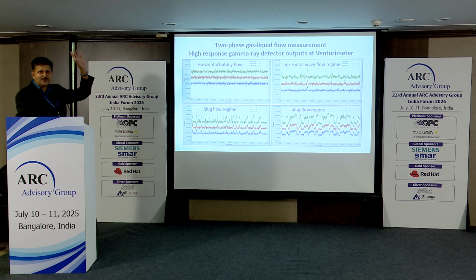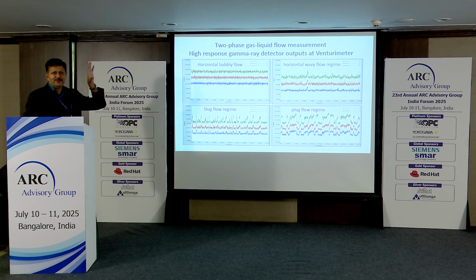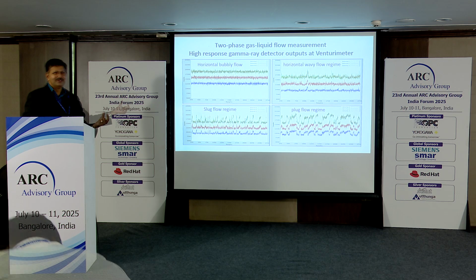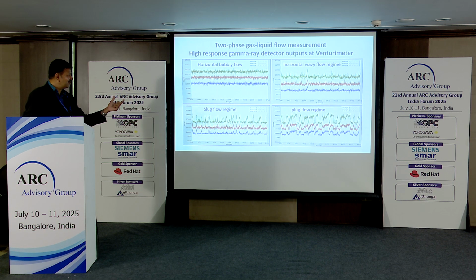It is a very classic design, like the old 1960s Framo design. So you have the mixture coming in to the homogenizer, and downstream of that, the gamma ray attenuation detection system is at the throat, so that you know exactly what is happening with the densitometer. Now the output is from the densitometer, and you can see that by observing the signals from the densitometer with high response, the x-axis is the time axis with data captured at 1 millisecond, right? So what you see is a 2 to 2.5 second time slot of horizontal bubbly flow, wavy flow, slug flow or plug flow regime going through the flow meter, and you are detecting this.